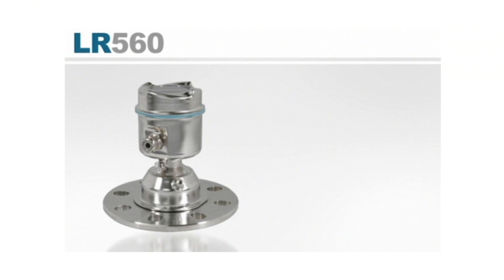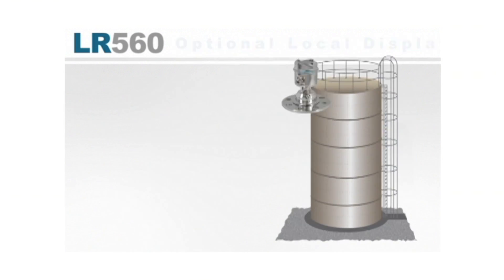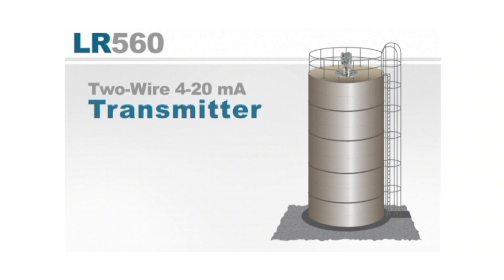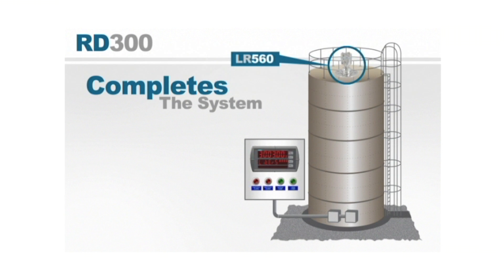The LR560 has an optional local display interface; however, in most level applications this display will be difficult to access for operators. The device is a two-wire 4 to 20 milliamp transmitter. The RD300 completes this system when combined with the LR560, providing the 24 volt DC loop power supply for the level indicator and displaying its 4 to 20 milliamp signal in a location more useful to the operator.